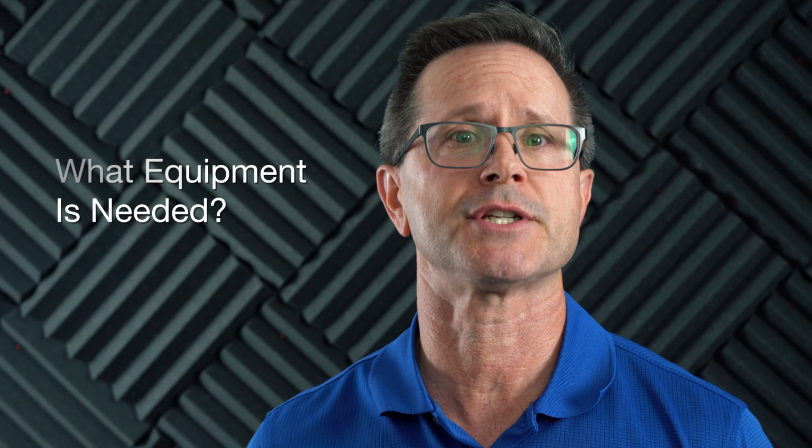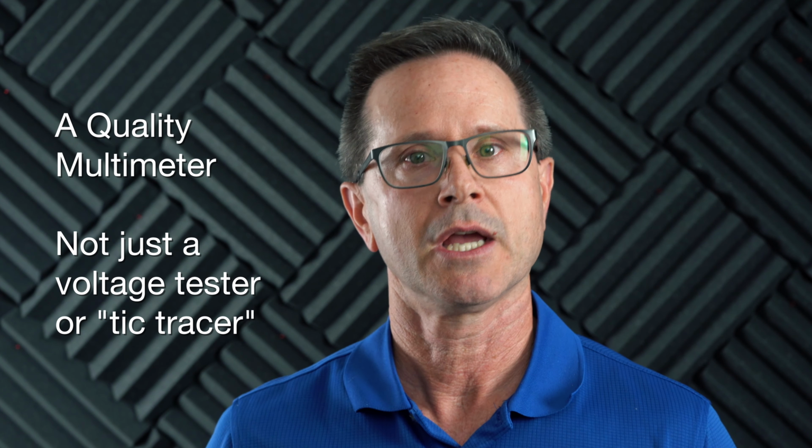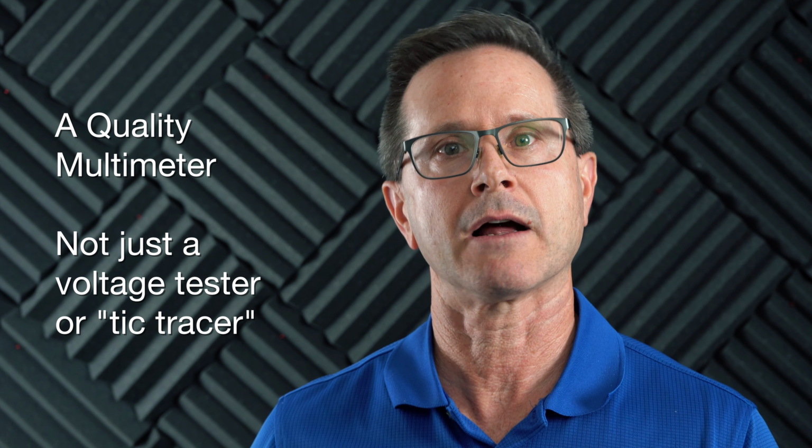The third thing is what equipment is needed. Because you have to make a decision: is this something that you can handle, or do you need to sub it out and call someone in? If you have the right equipment, a lot of times you can walk through and figure this out yourself. So if you know that several lights are out, and you know it's fed from this lighting panel, some of the equipment that you might need is a good multimeter. Not just a little tracer that detects voltage, but a good multimeter that allows you, when you take the cover off, to say, do I have power at the panel? Do I have power leaving the breaker?